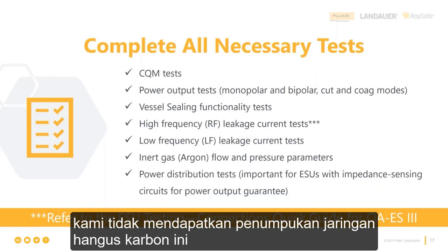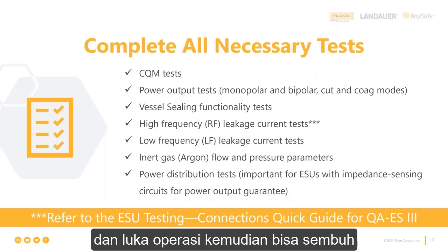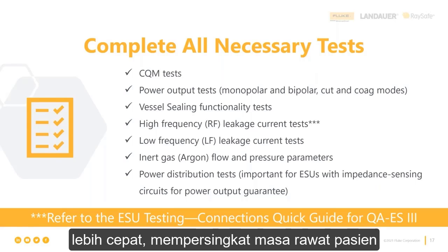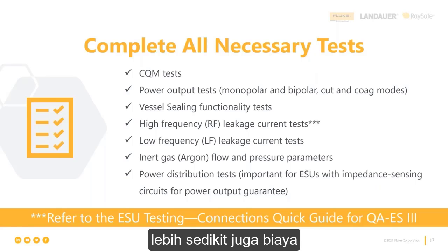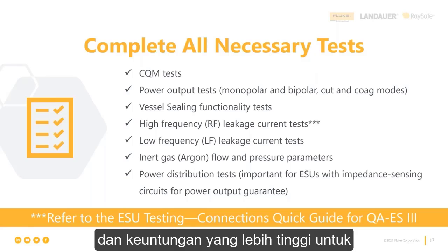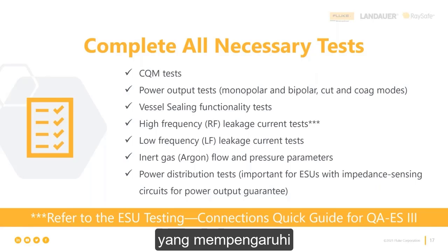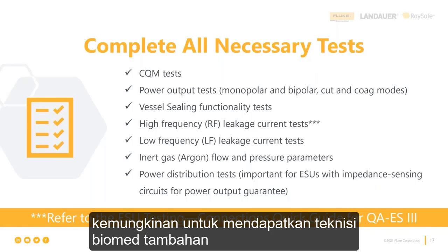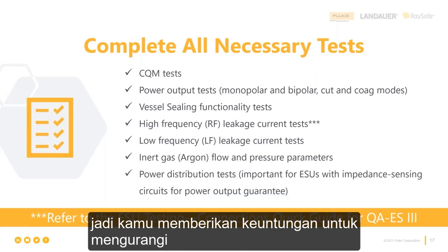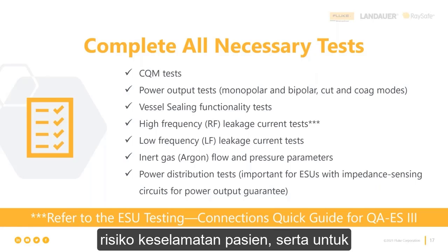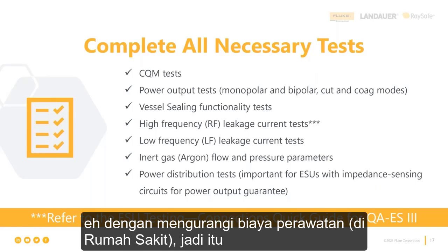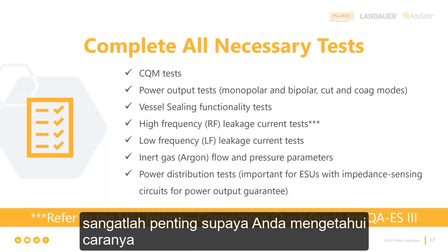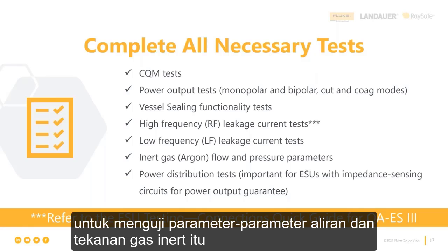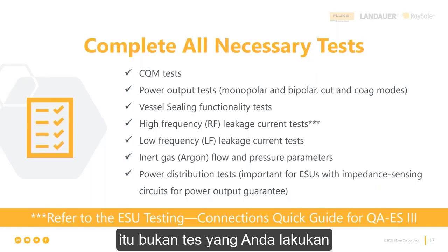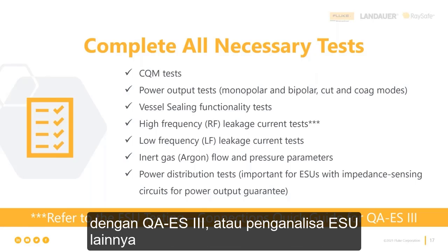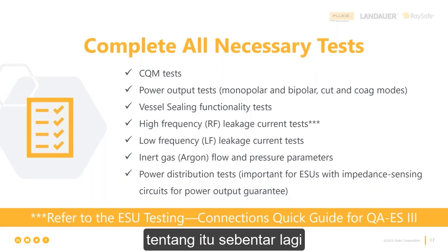So we don't get carbon buildup charring, and the surgical wounds then heal faster, shortens patient length of stay, less cost of care, and higher profitability for your hospital. And guess what? That affects that you can get paid, or that you can get that next extra biomed tech that you need. So you're playing both to the patient's safety, risk reduction, as well as to reducing the cost of ownership by reducing cost of care. So it's really important that you know how to test those inert gas flow and pressure parameters. That's not a test that you do with QA-ES3 or any other ESU analyzer. You need something else, and we'll talk about that in a minute.